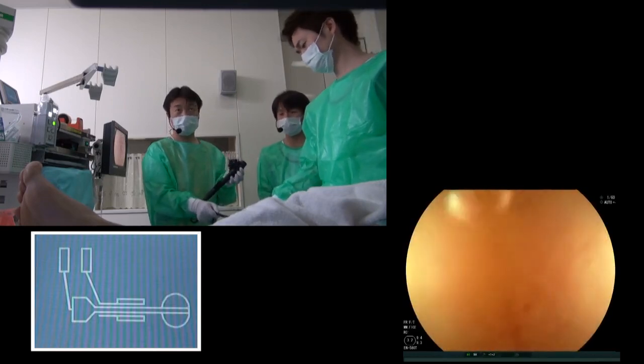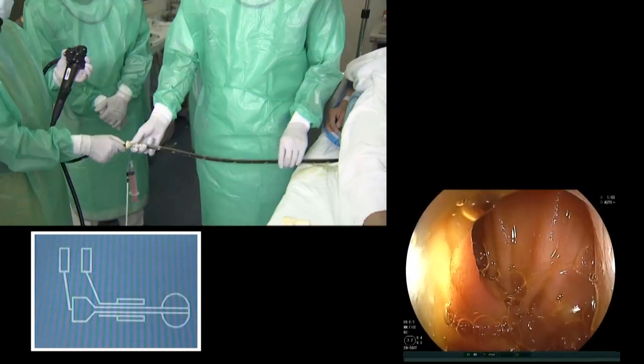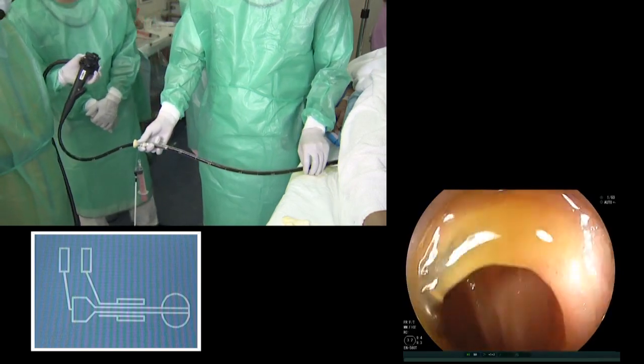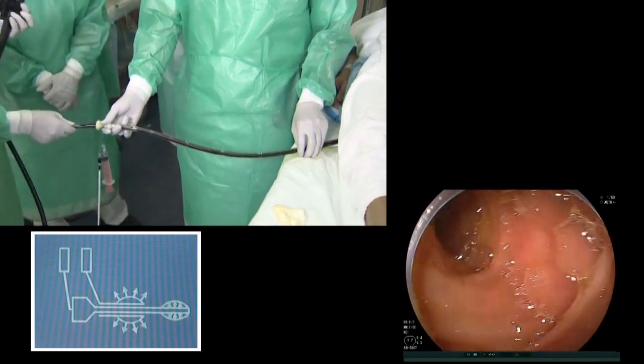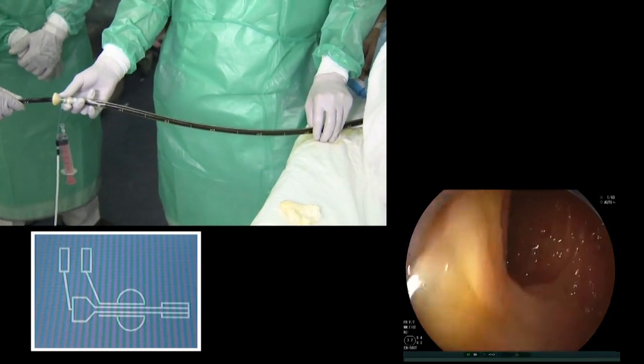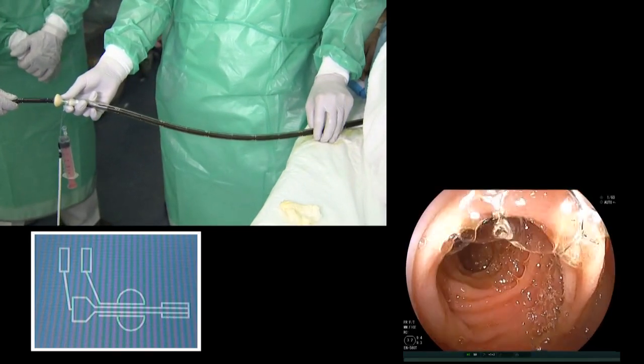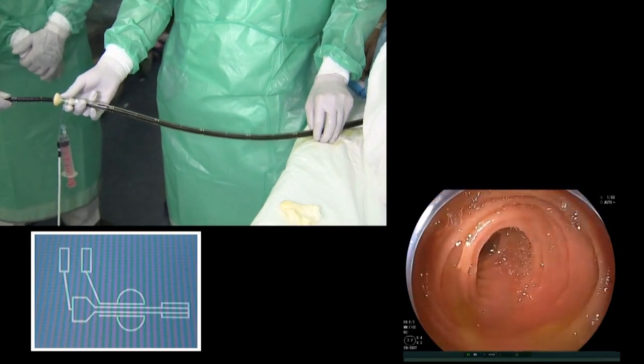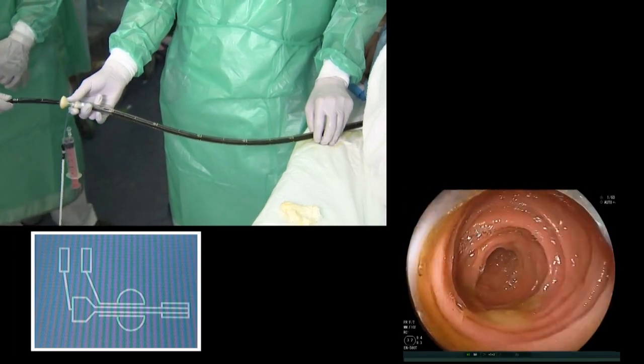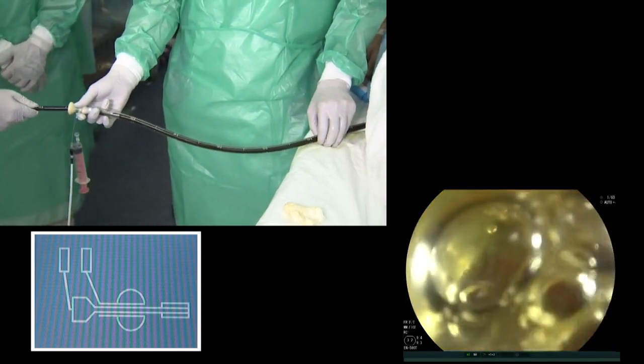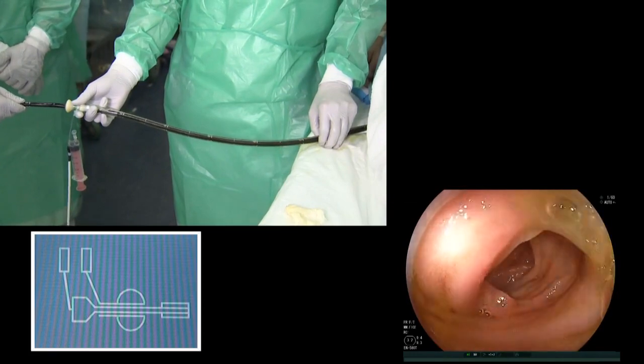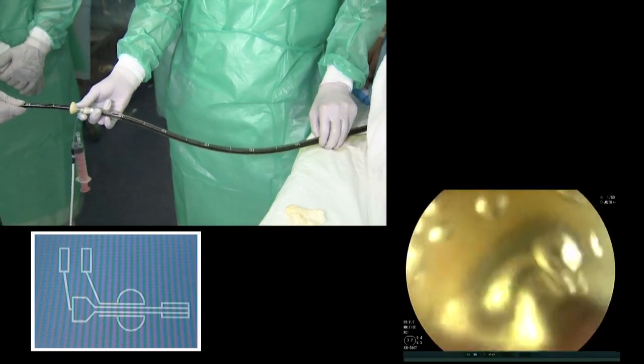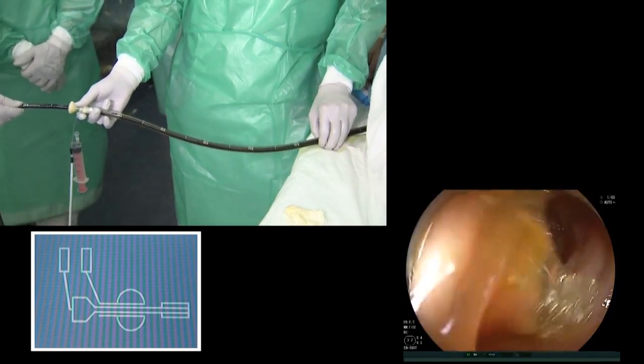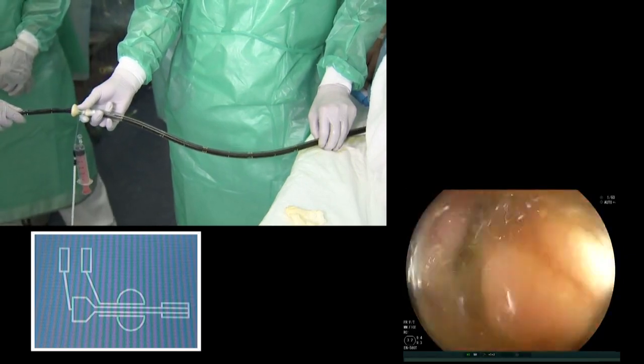During the inspection phase, if the overtube is withdrawn over the entire length, the intestine pleated on the overtube will rapidly uncoil and lose its manipulability. That is why we move back the overtube by 10 centimeters at a time to allow controlled release of intestine for inspection. Because on each 10 centimeter length of overtube, about 30 centimeters of intestine is pleated.